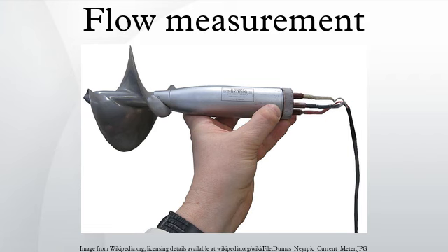One can also calculate the expected speed of sound for a given fluid. This can be compared to the speed of sound empirically measured by an ultrasonic flow meter for the purposes of monitoring the quality of the flow meter's measurements. A drop in quality is an indication that the meter needs servicing.